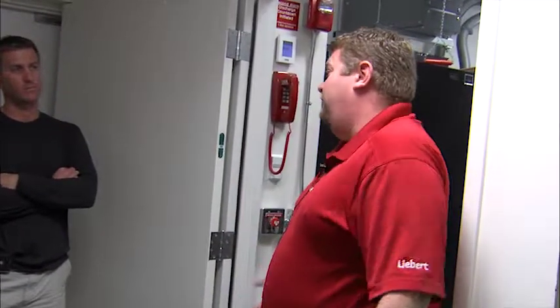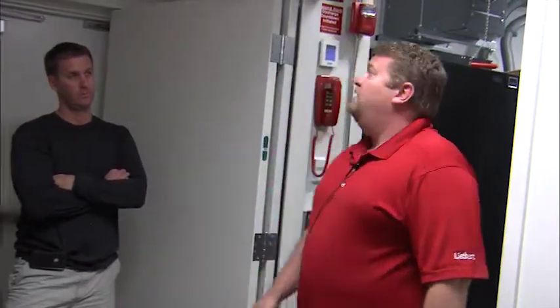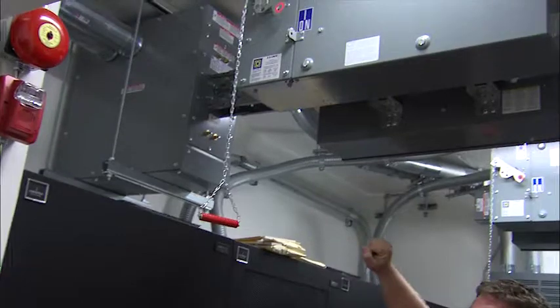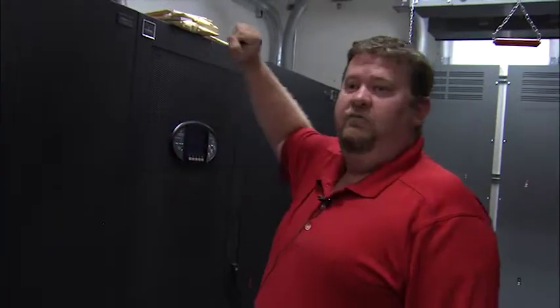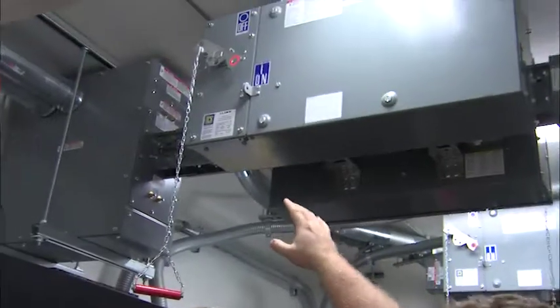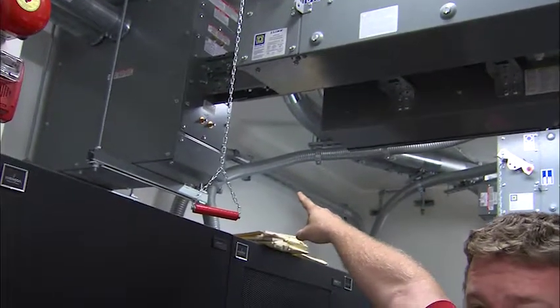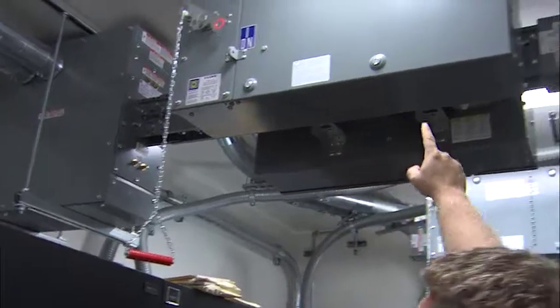And again, that's the worst case scenario. In 16 years, I've never had to do that, but we build it in for Tier 4. So above here, we have our input and output, what we call bus duct. Basically, this is 800 amp bus with 400 amp input and outputs. So once the system was either EPO'd or put into bypass completely, because, and this is critical, and again, you won't ever have to do this, this is for Liebert, or excuse me, third-party service.